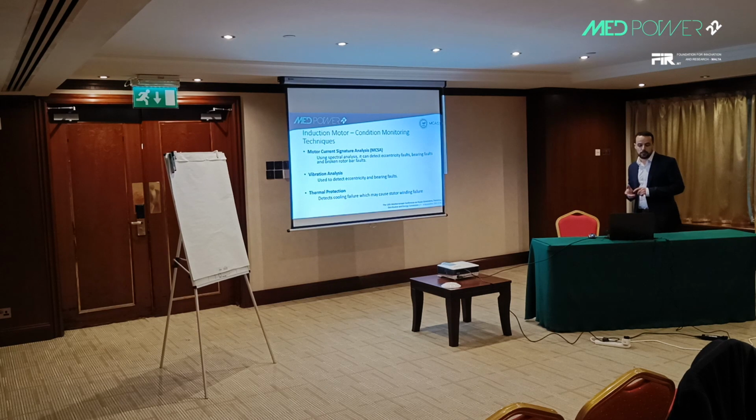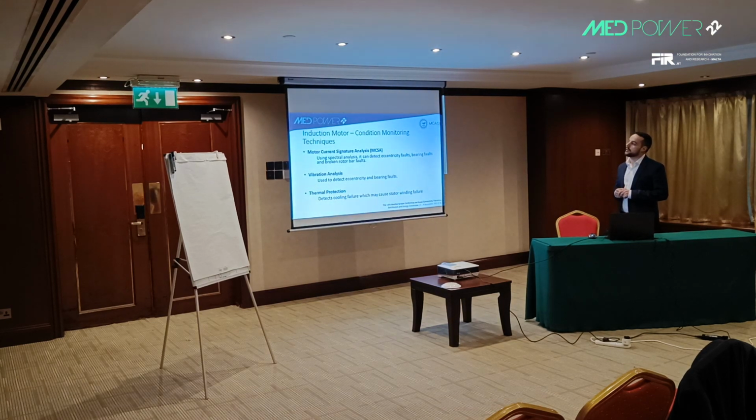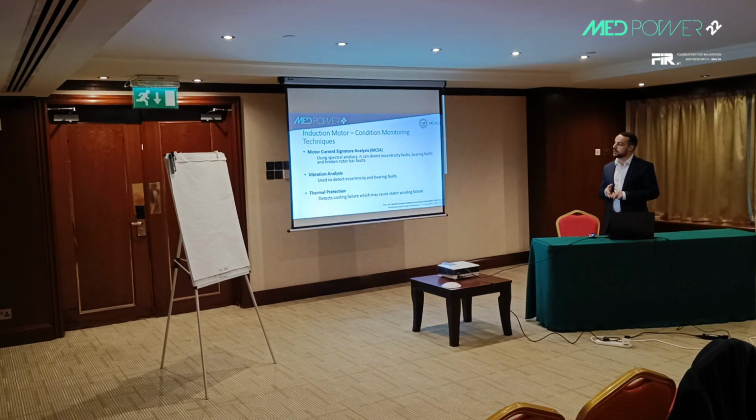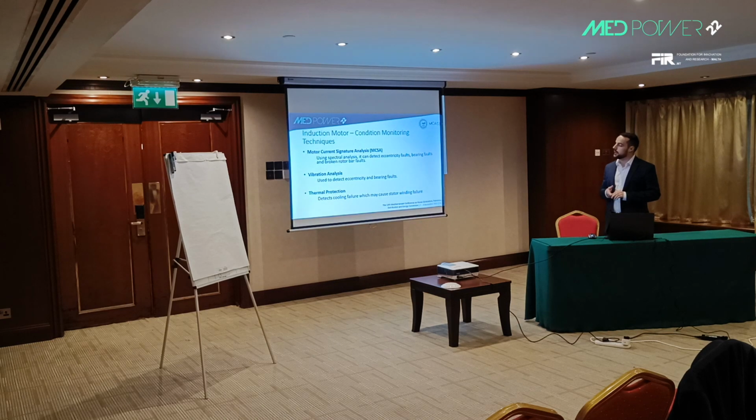Now, in this paper we used three techniques to detect these faults on the induction motor, namely motor current signature analysis, which uses spectral analysis to detect eccentricity faults, bearing faults, and broken rotor bar faults. We also used another analysis tool, vibration analysis, to detect eccentricity and bearing faults. Also, thermal protection is important to prevent catastrophic failures from stator winding insulation short circuits.